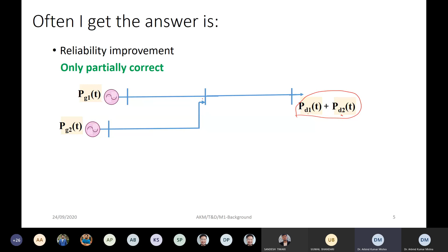In addition to that, the reliability improvement does not just happen if you simply interconnect things. You need some additional cost. For example, I mentioned earlier that if this generator fails, then this generator can meet both the demands. For that purpose, the requirement is that this generator must have sufficient capacity to meet both demands, the sum of the demands, by PG2 itself. For that purpose, we need a sufficient reserve margin. Similarly, this transmission link, from here to here, should have the capacity for the power flow of both demand one and demand two.